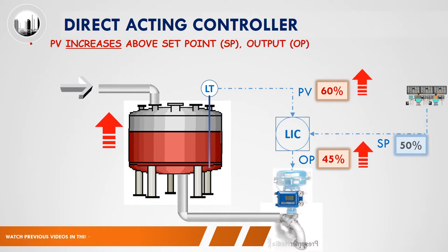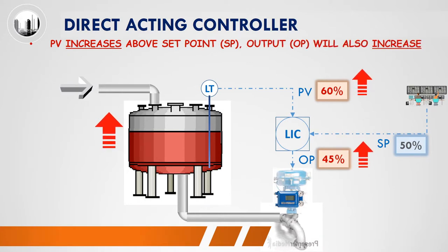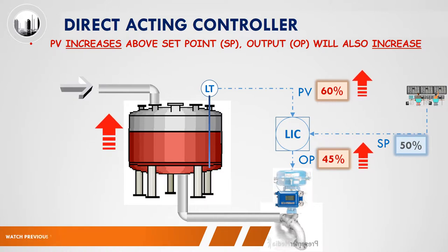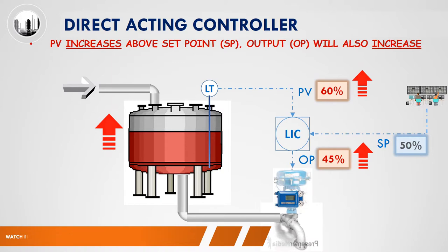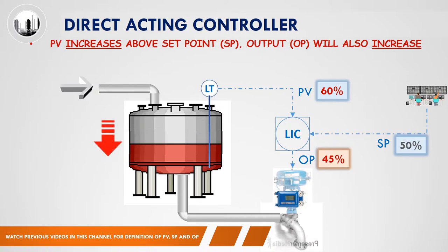Thus, for a direct acting controller, when the current process variable or PV increases above the set point or SP, the output or OP will also increase. With the larger opening of the control valve, the tank level will reduce back to the set point.